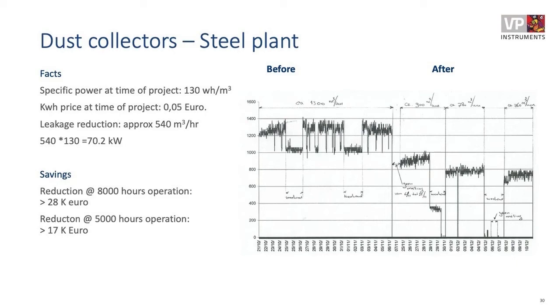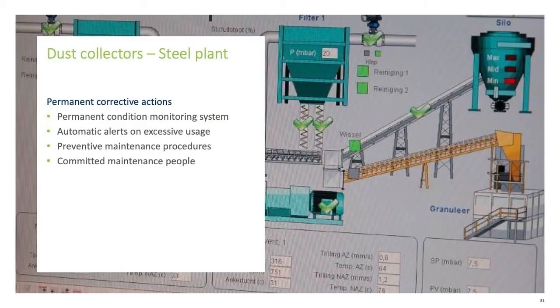So after this initial audit and initial repairs, they decided to take a couple of permanent corrective actions. They implemented a permanent condition monitoring system, and they tied it into the PLC or SCADA system that monitored the entire plant, including those filter towers. They got automatic alerts on excessive usage. And very important, they also implemented the maintenance procedures, because you can get an alarm, but you still have to act on it. And thanks to committed maintenance people, they were able to maintain that savings level.